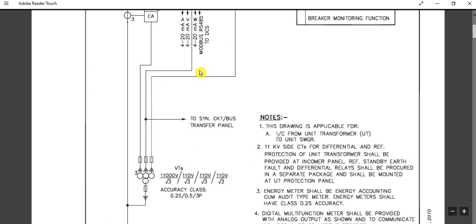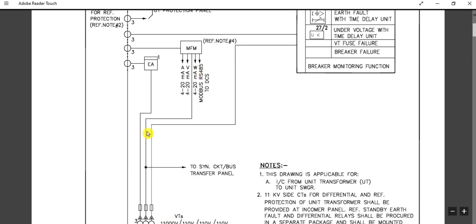The 0.2S accuracy class VT winding is connected to the EA (energy audit meter). The CT current signal for the energy audit meter also has a 0.2S accuracy class, which provides better accuracy. The 0.5 accuracy class VT signal goes to the MFM (multi-function meter), with the current signal also coming from a 0.5 accuracy class CT winding.